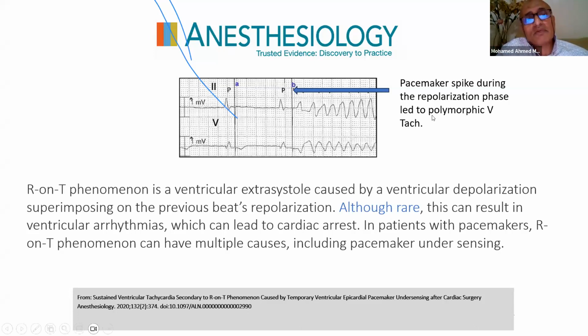Why? It may be due to the strong electromagnetic field beside the device. It affected the function of the device, and it prevented the device from returning to the synchronous mode after removal of the magnet. So if we use a magnet, we have to confirm that the device returned to its function. The only way for confirmation is reinterrogation of the device by the CIED team in the recovery room or in the ICU.